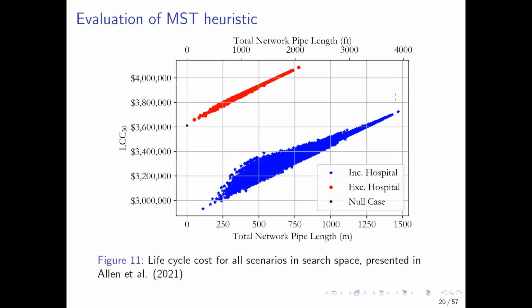A bifurcation exists as to whether the prototypical hospital building is served by the network, with scenarios where the hospital is served by the network having significantly lower life cycle cost. That results because only that building type exhibited a reduction in energy cost from connection to the network, driven by significant reductions in energy use intensity, which offset the increase in energy costs due to the higher unit cost for heating with electricity relative to natural gas in this location in the US, and in many areas of the US.